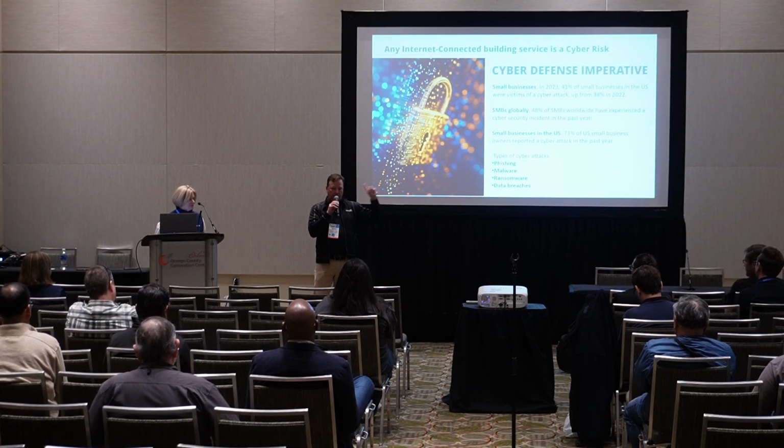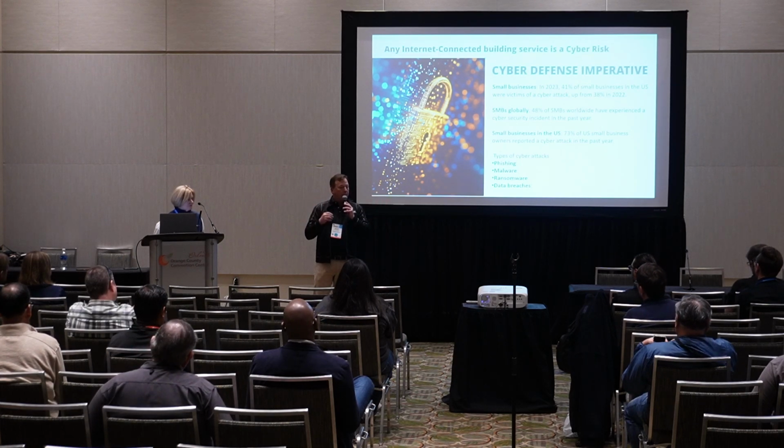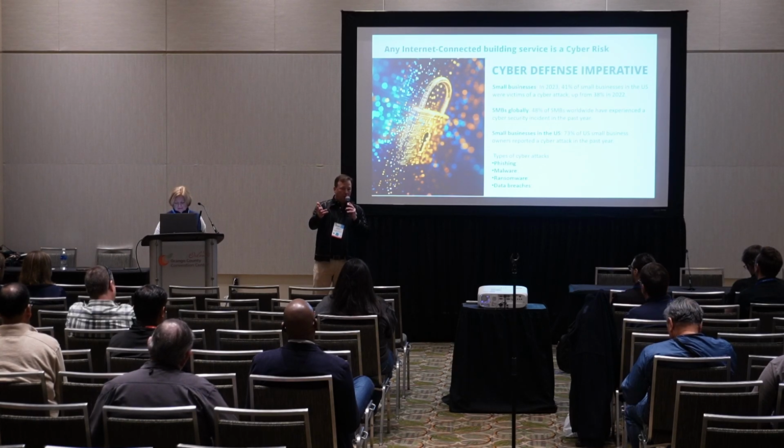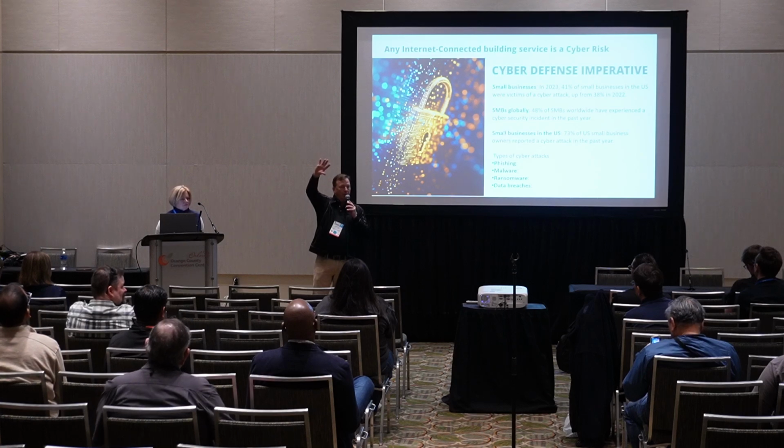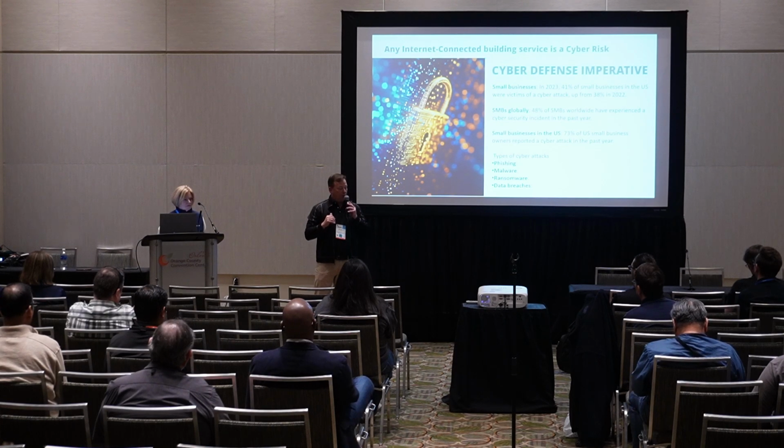The first thing is the connection to the internet. That is always the first thing to look at. And is it protected? Is a VPN the right way? Maybe. They now say no. There's a new methodology called Zero Trust. Zero Trust is a VPN plus. It's kind of like a VPN, but now when you come into the network, it doesn't just let you into the whole network. It only gives you certain paths within the network, restricting your flow, and again, adding safeties along the way. So a Zero Trust network connection is something to consider if you want to remote connect to an owner's building, all right?